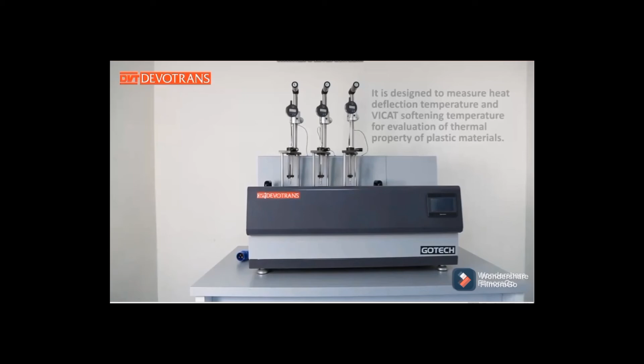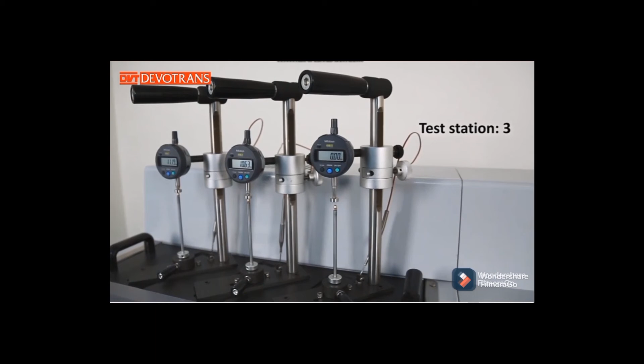Let us try to explain our equipment with the help of a video. This is a 3-station tester that will run 3 samples simultaneously and show separate results. These are the 3 stations on which the samples will run, and each station contains a separate display. This is a deflection measuring sensor with digital indicator, and here the output result will be shown. This is the PID controller on which the temperature range of ambient temperature to 300 degrees C is maintained. This equipment also contains the cooling method through a water piping system as our precautionary measure.